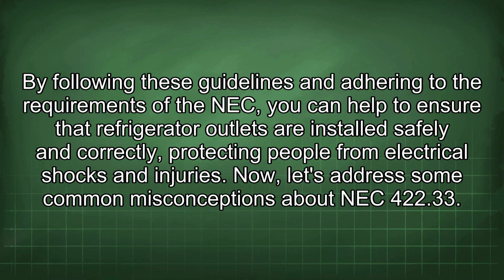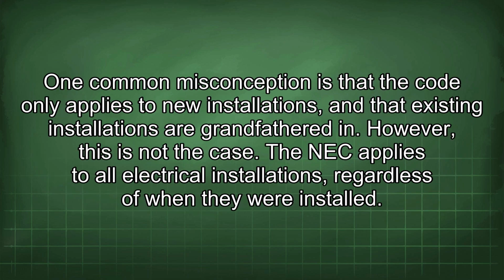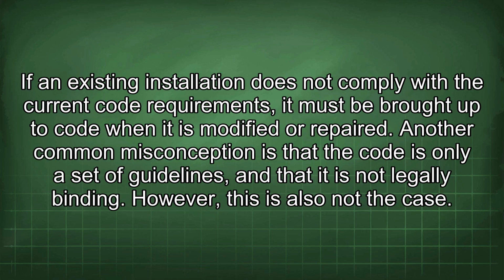Now, let's address some common misconceptions about NEC 422.33. One common misconception is that the code only applies to new installations, and that existing installations are grandfathered in. However, this is not the case. The NEC applies to all electrical installations, regardless of when they were installed. If an existing installation does not comply with the current code requirements, it must be brought up to code when it is modified or repaired.